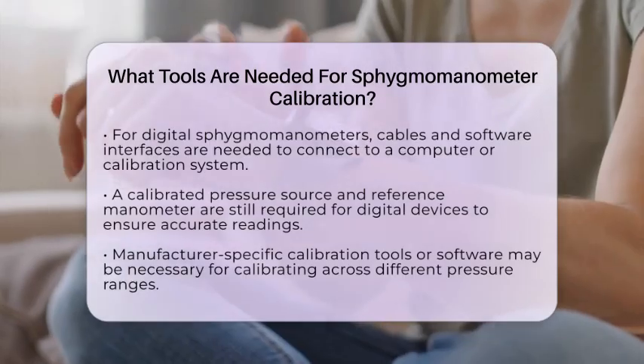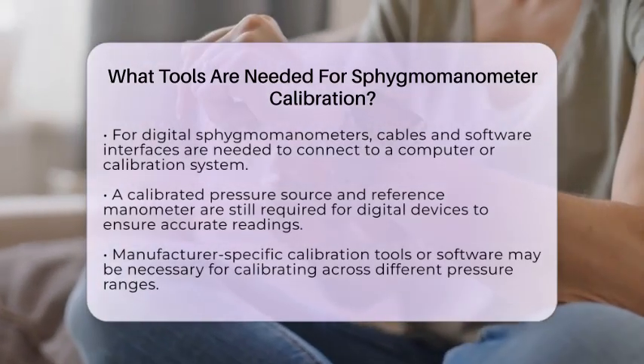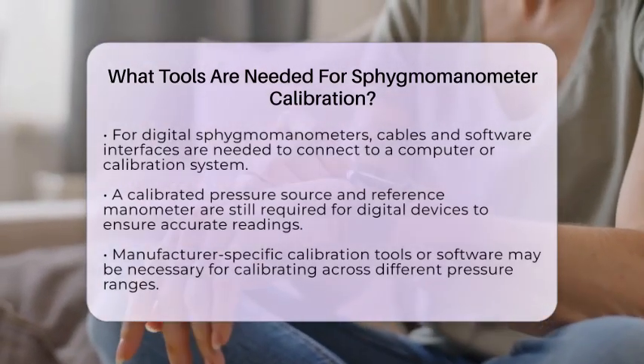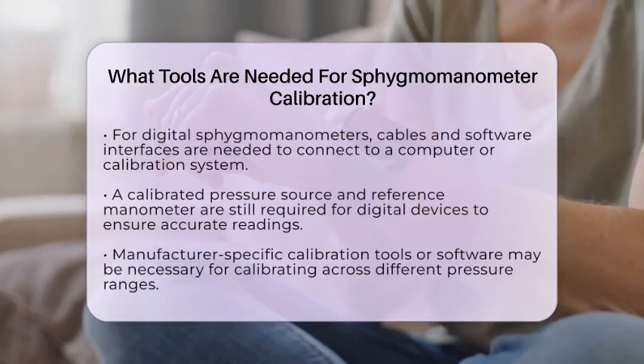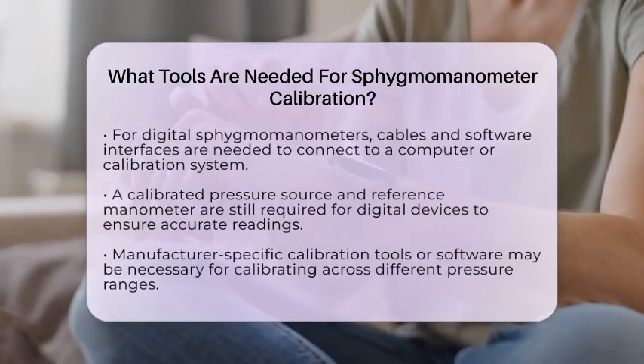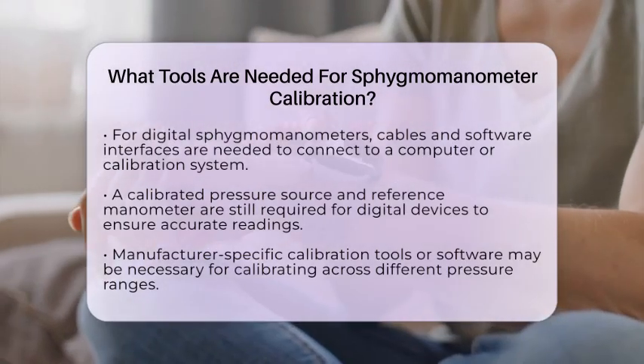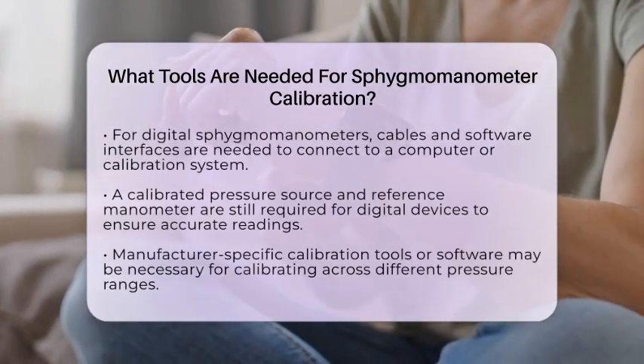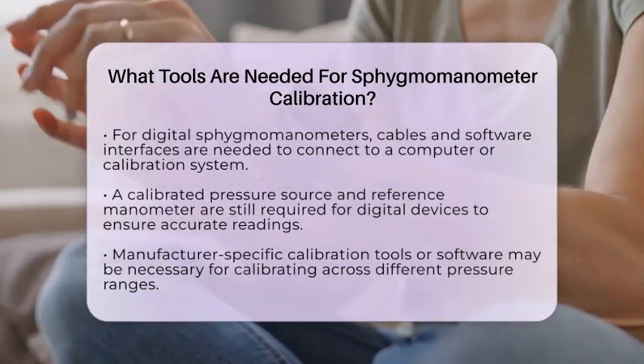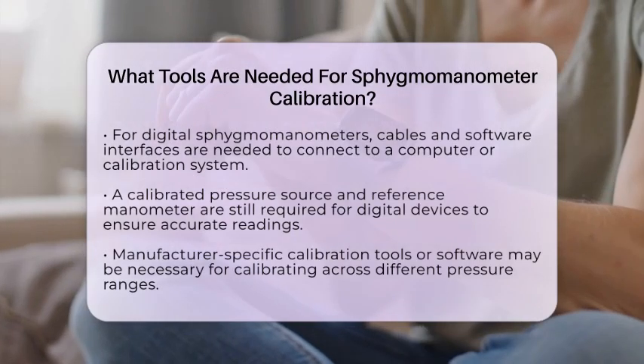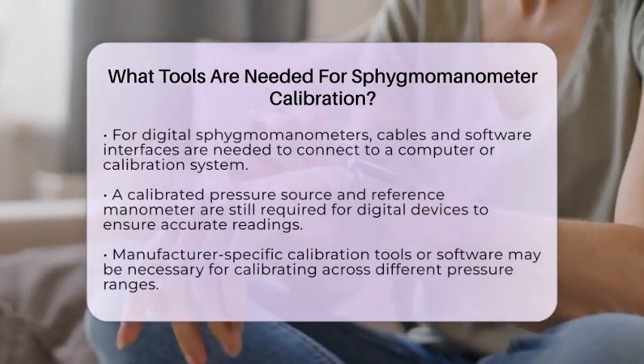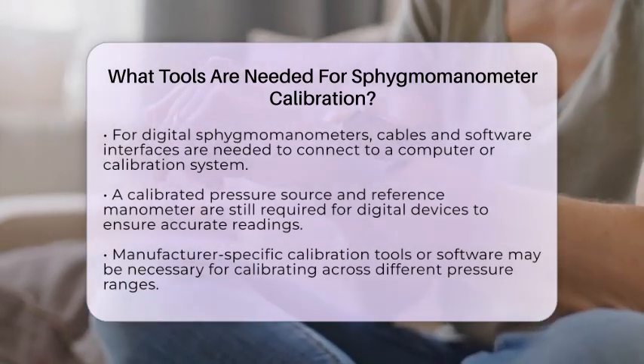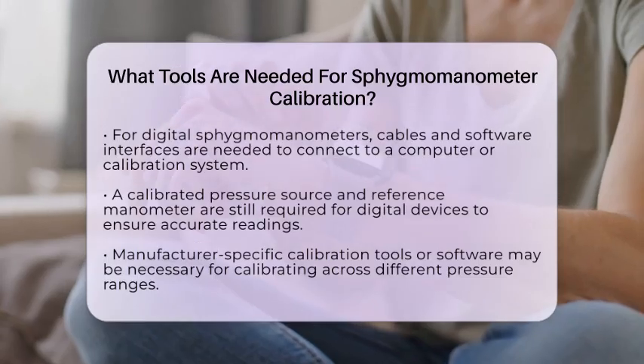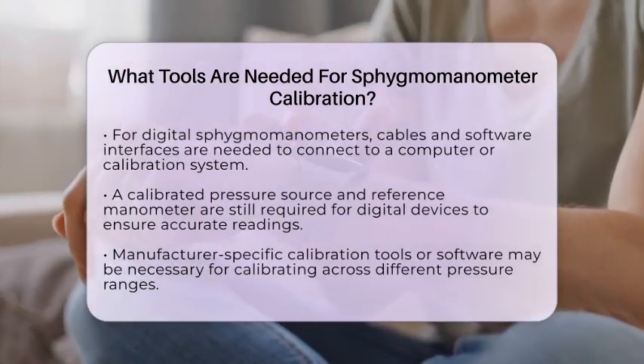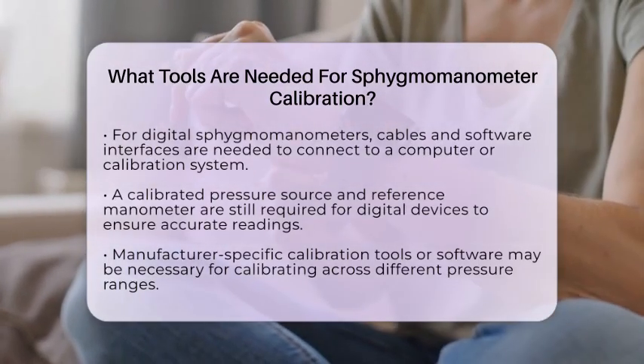For digital sphygmomanometers, the calibration process involves connecting cables and software interfaces. This links the device to a computer or calibration system. You will still need a calibrated pressure source and reference manometer to compare and adjust the digital readings. Additionally, manufacturer-specific calibration tools or software are often required for low, middle, and high-pressure range calibrations.